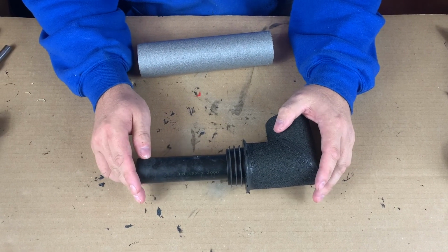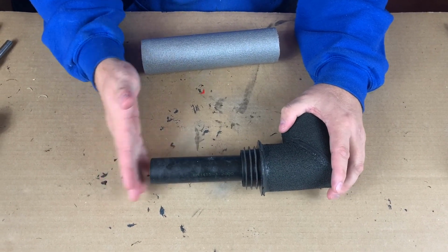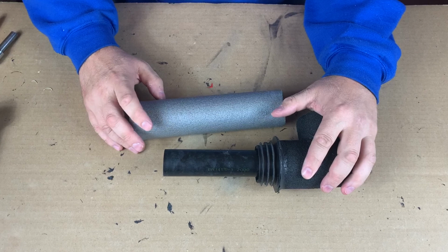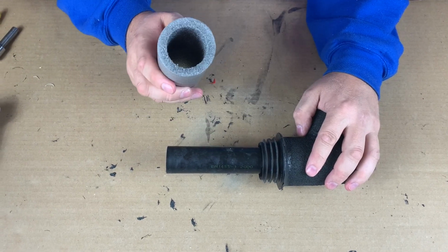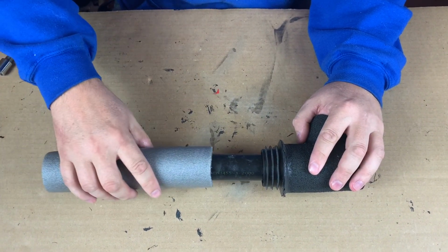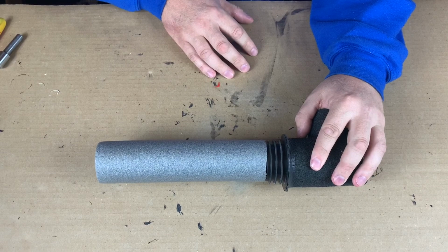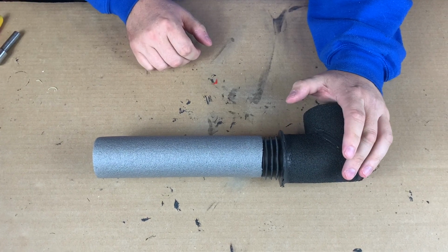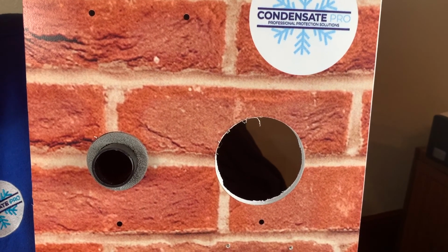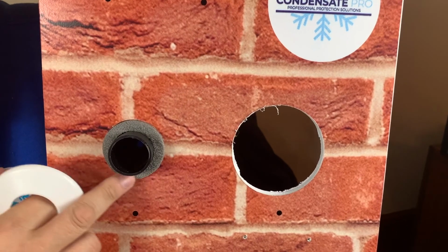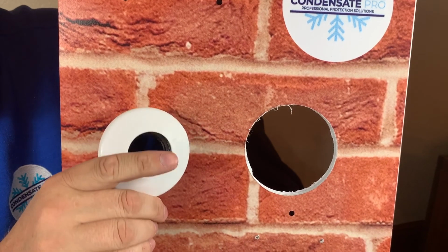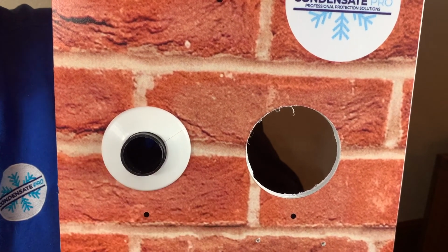So other instructions that could be in the manufacturer's instructions state that we may have to insulate inside the cavity wall to protect it. If you just use some standard Tubolite 9mm wall thickness and use the 52mm core all the way through, that then pushes through and seals to the pipe snug and then seals all the way through the building. We've come in with the insulation inside the property, and what we could have a problem with is trying to seal around that. Talon do a cover, and that comes in all different colours, and that could be easily put round there and make a lovely seal.